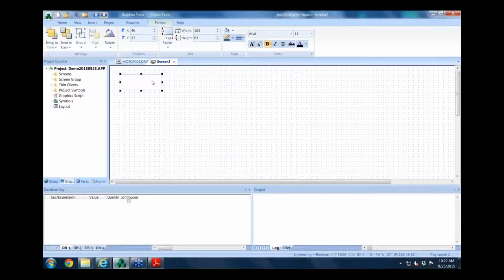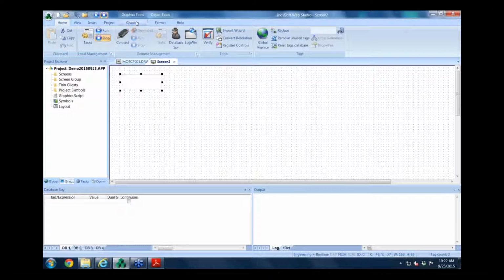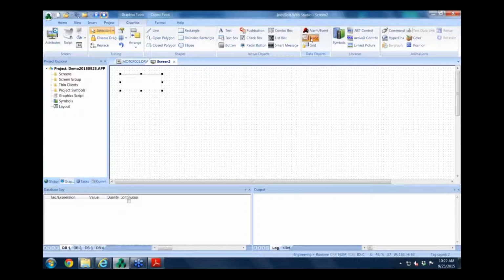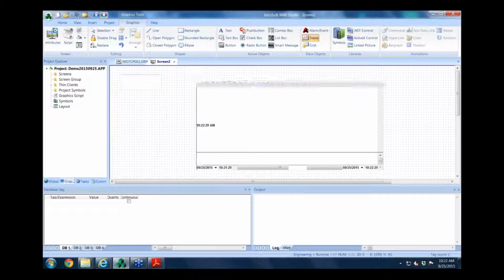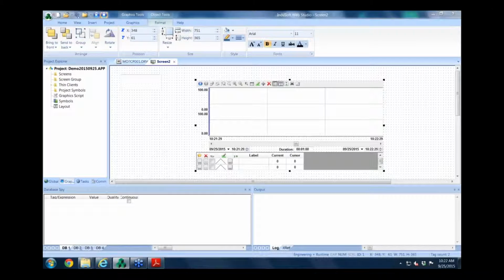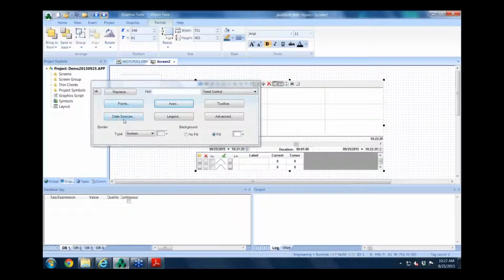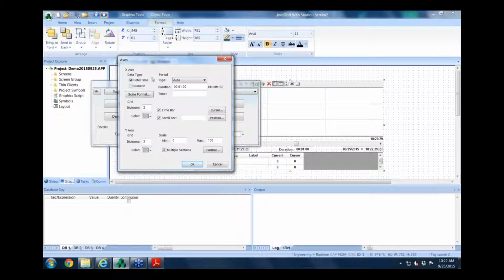If you want to do a trend curve, go back to the graphics tab and click the trend icon, draw your box, and double click for properties like points and data source. You can adjust your axes by clicking the axis box and putting your minimum and maximum scale. For instance, temperature between negative 32 degrees and 212, and select your number of divisions on the y-axis.